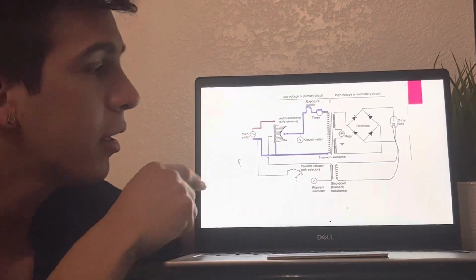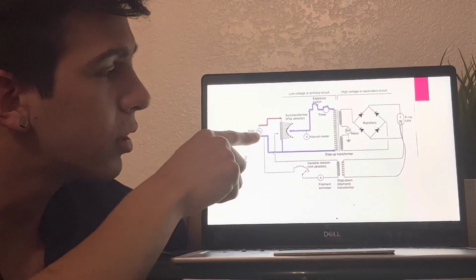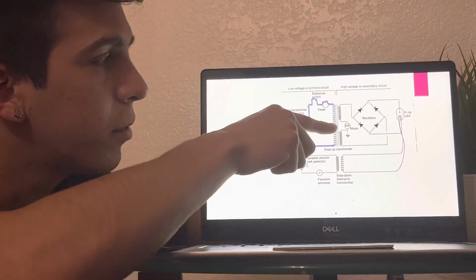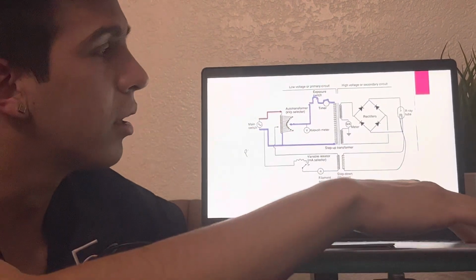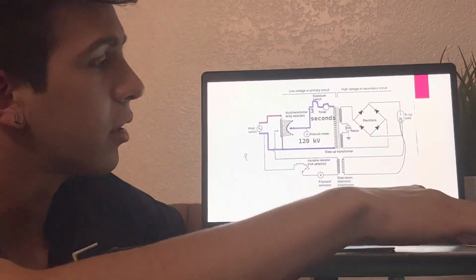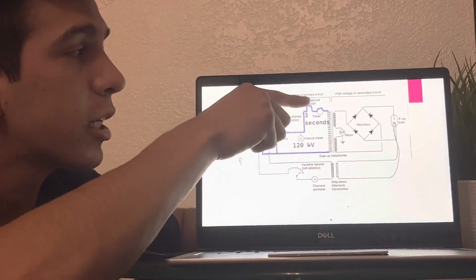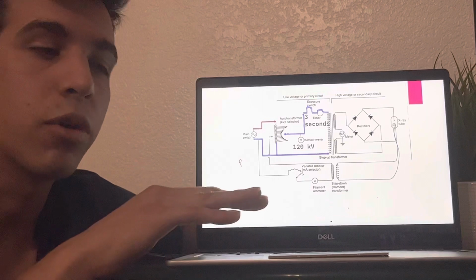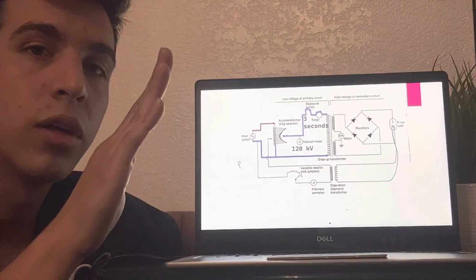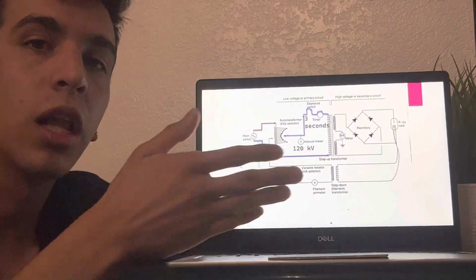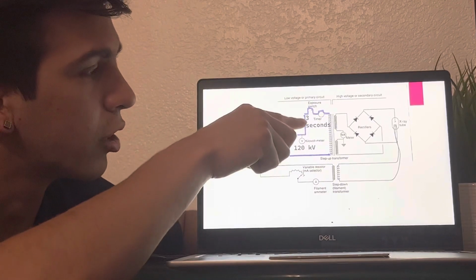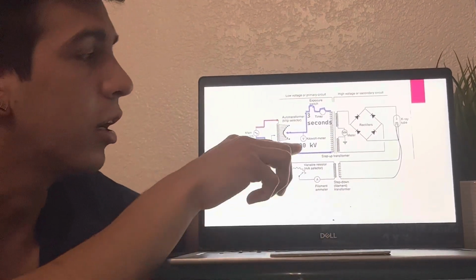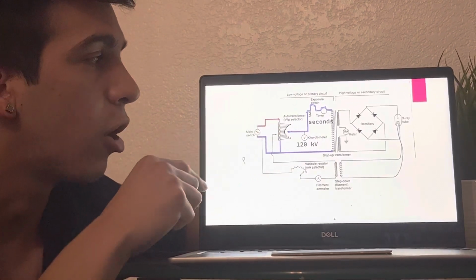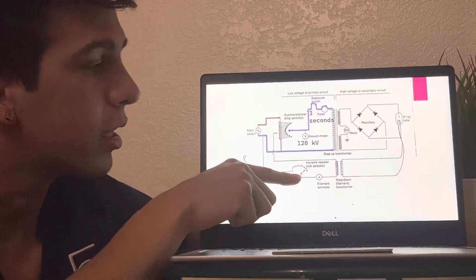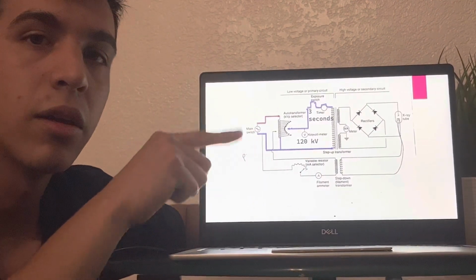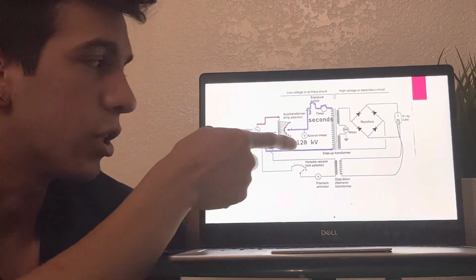The next part I'm going to be discussing is these two currents. This one is going to do the same thing. It's going to flow all the way up these coils and then through the timer. The timer is going to be 3 seconds, just like so. And it's going to go through the exposure switch. The exposure switch is basically a drawbridge. It's usually going to be raised up until everything is set in place. Then it's going to go down and allow the current to flow in for those 3 seconds. It's going to go over to the kilovolt meter, which measures that it's the correct kilovoltage, which is 120, and then flow into the auto transformer. The auto transformer is going to do the same thing as the variable resistor. It's going to be selecting based on the settings that we put into the machine, which is 120 for this example.